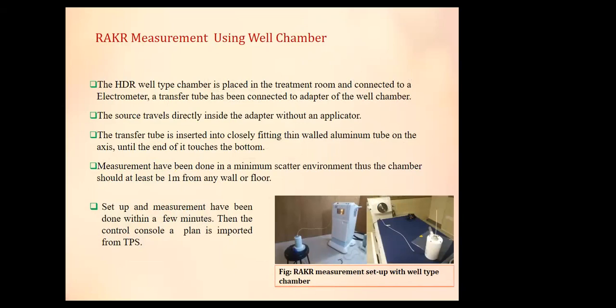Now I explain the reference air kerma rate measurement using the well-type ionization chamber. I used cobalt-60 and iridium-192 sources in different hospitals. One is the Varian GammaMedPlus, and another is the VariSource multi-source unit. The high dose rate well-type chamber is placed in the treatment room and connected to the electrometer. A transfer tube is connected to the adapter of the well chamber. The source travels directly inside the adapter without an applicator. The transfer tube is inserted, closely fitting, into the thin-walled aluminum tube on the axis until the end touches the bottom.